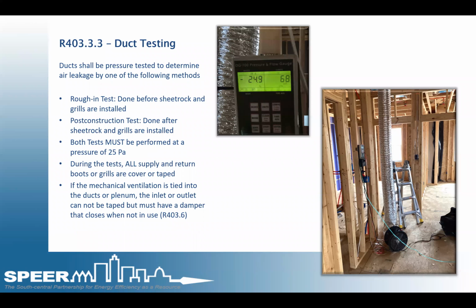However, the blower door testing procedure states that the inlet or outlet can be sealed during the testing if it's continuous. So you kind of interpret that into saying one way or the other, it needs to have a damper that closes when not in use. In my opinion, with a much smaller volume of air being tested during duct testing compared to a whole house target like a blower door, the duct system should be tested as it would be in normal operations and not allowed to give a false test result by allowing a portion of the system to be taped, which would otherwise not be during normal operations. Lastly, a written report of the testing results must be signed and provided to the code official.